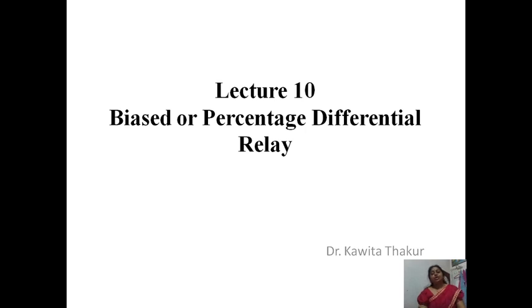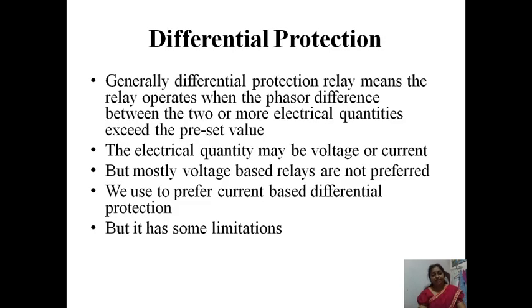In the last lecture, you studied differential protection. Generally, a differential protection relay operates when the phasor difference between two or more electrical quantities exceeds a preset value. The electrical quantity may be voltage or current, giving us two principles: circulating current principle or voltage balance principle. But mostly voltage-based relays are not preferred; we prefer current-based differential protection, i.e., the circulating current principle.